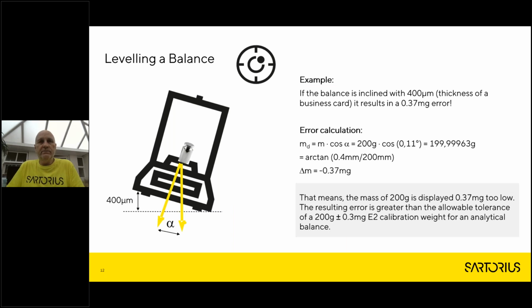We all know that a balance should be level before you use it to weigh, but what sort of an error does this introduce if the balance isn't level? This is a small example of how much error can be generated by a balance which is not leveled. So in this example, by placing a small business card under the feet of one of the balances to develop an out of level scenario, we're looking at a 400 micron lift on one side of the balance, and that generates a 0.37 milligram error, so 370 micrograms of error into your weighing process. You can see there in the calculation. I'm not going to go into details, but the error is the cosine of the angle which is developed from the vertical to the new line through the balance on its inclination.